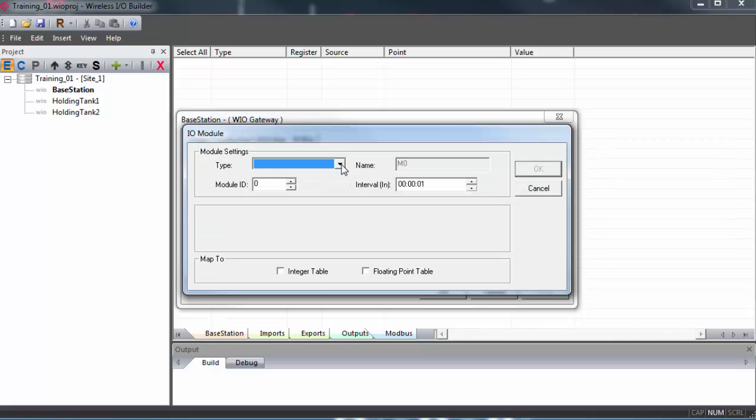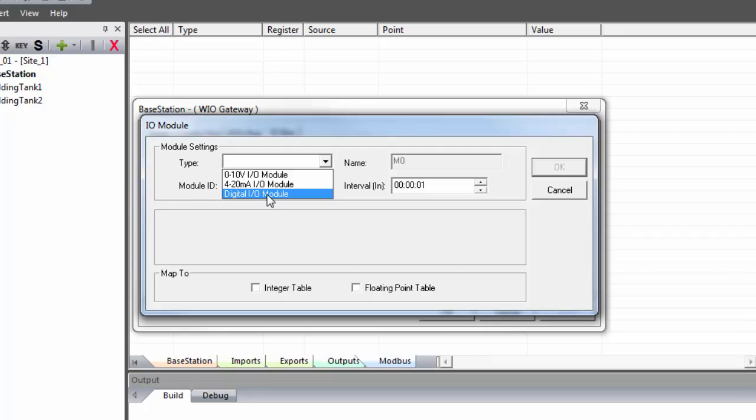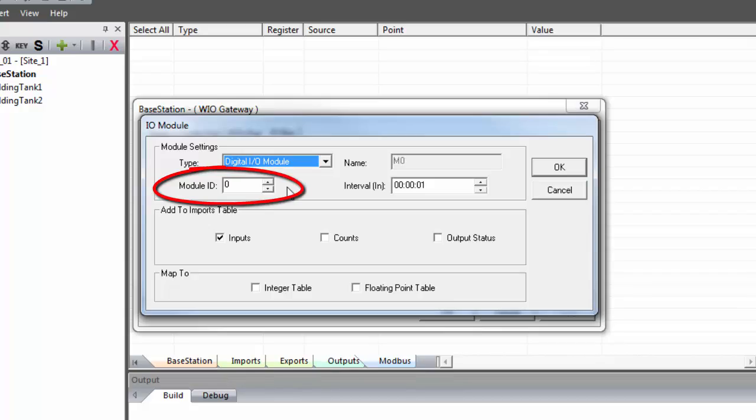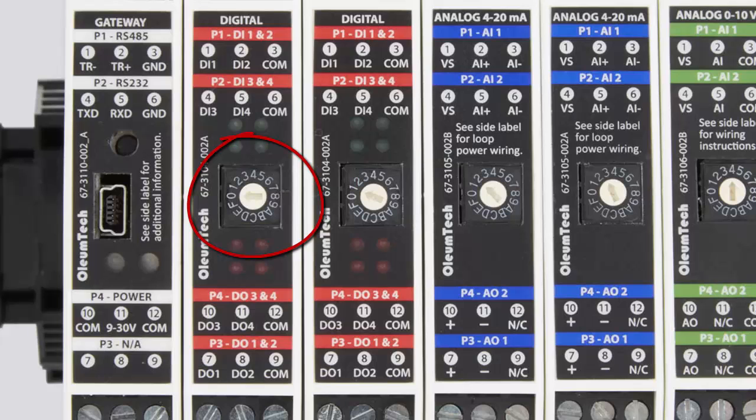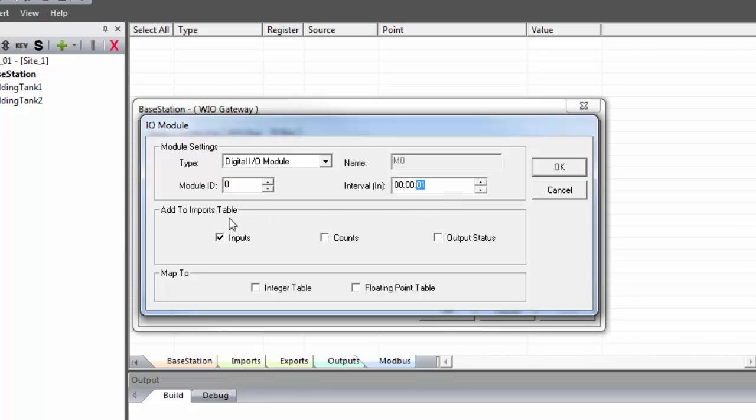So with that in mind, we'll go to the IO bus tab, click New, and select an IO module. We have three different modules to choose from. In this case, we'll go with a digital IO module. Under module settings, we need to set the module ID to match the dial setting on the module itself. Each module in the group must have its own unique ID. Note that the module ID dial cannot be reset with the power on, so you can't set it to a different ID on the fly. It's because the ID is only read by the gateway once on startup.